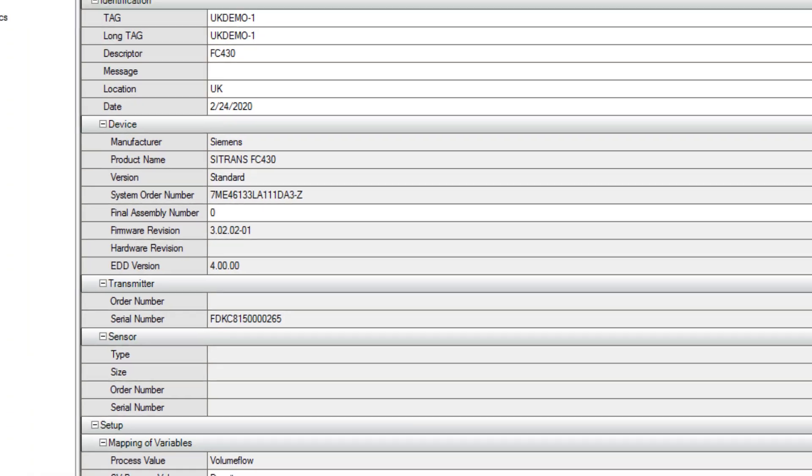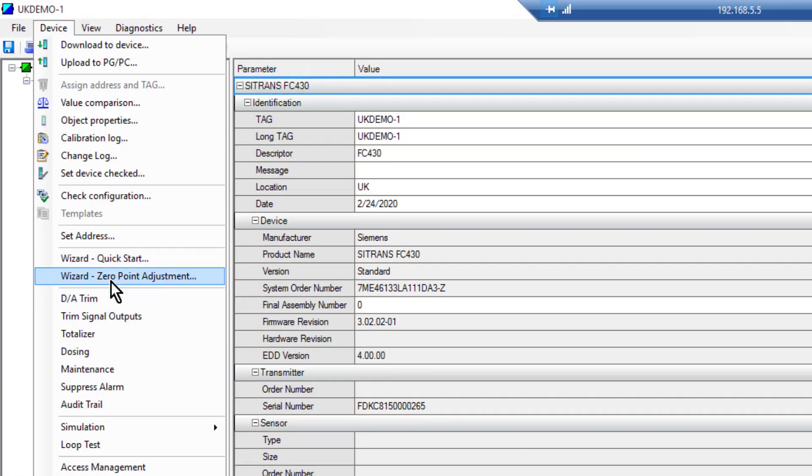It's recommending here to do a zero. Use this with extreme caution—there's another wizard for doing a zero point calibration. You've got to be 100% sure that your pipe is full with liquid or air, depending on whether it's gas or liquid application, and definitely for liquid that you have trapped the operating pressure in there or at least a back pressure of 200 millibar. That's pretty consistent for Coriolis meters. If you don't meet those conditions and you zero the flow meter, then you're going to have issues.